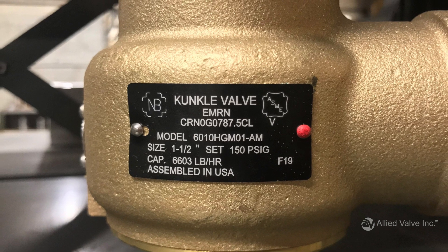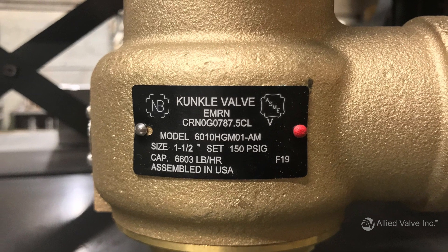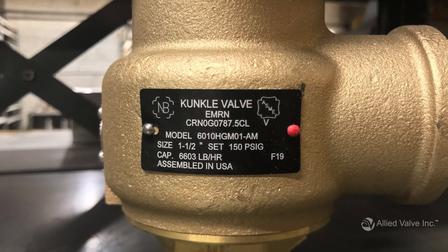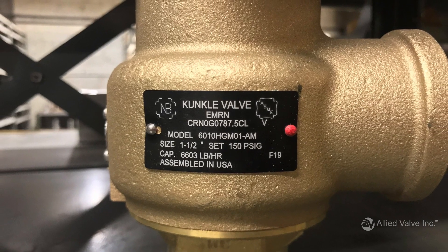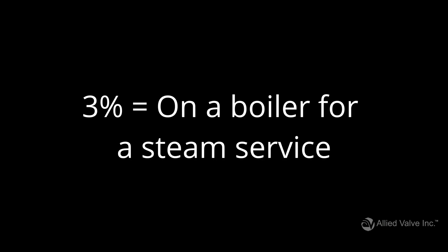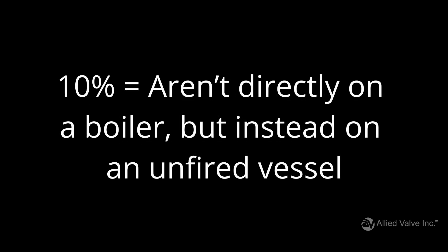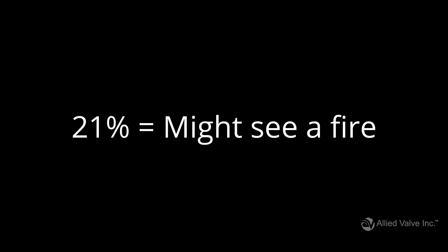Your allowable overpressure helps determine the valve's code stamp and generally depends on where you're using the valve. There are three options for allowable overpressure: three percent, ten percent, and 21 percent. Three percent is for valves that are on a boiler for a steam service. Ten percent is for valves that aren't directly on a boiler, but instead on an unfired vessel. And finally, 21 percent is for valves that might see a fire.